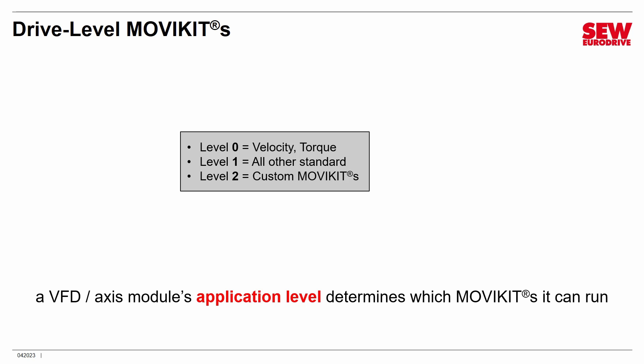A level 0 VFD, the least expensive, can run the velocity and torque control MOVIKIT's. To run the others, you upgrade to level 1, which runs all the standard ones. SEW EuroDrive can also create custom MOVIKIT's written in DataFlex for customers, but running those requires application level 2. For most purposes level 1 is sufficient, though level 2 gives you complete flexibility.